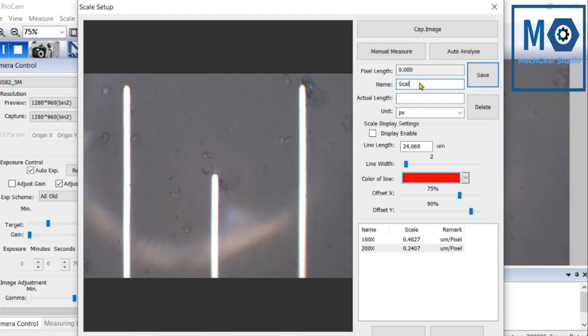Once we calibrate all magnifications, it is not required every time. It will be preserved in the system and we can apply it directly. So this is a first time exercise. When we are using the software for the first time, this is a first time activity. Then the same calibration can be used in actual microstructure measurement.